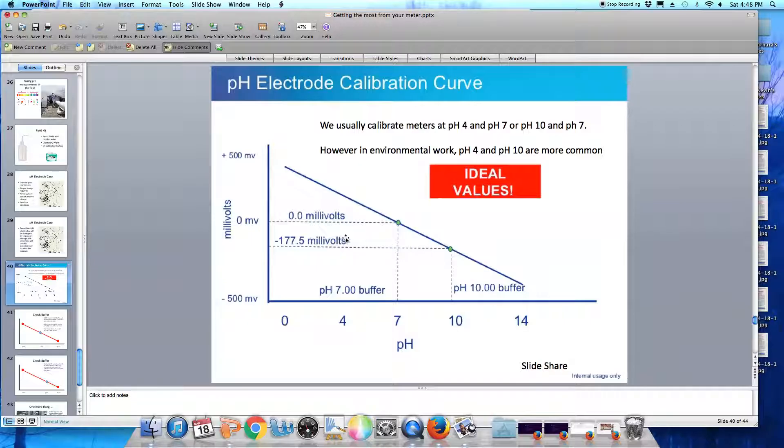The second buffer we would put our probe in for calibration would be, in this example, pH 10, which will generate a millivolt signal of minus 177.5 millivolts. So any pH reading we make between pH 7 and pH 10 will have a millivolt value somewhere between 0 and minus 177.5 millivolts.